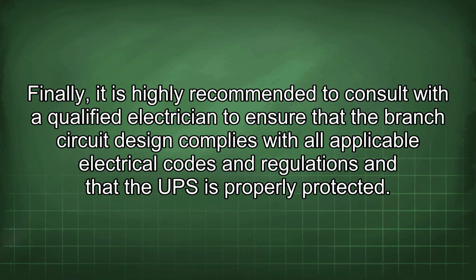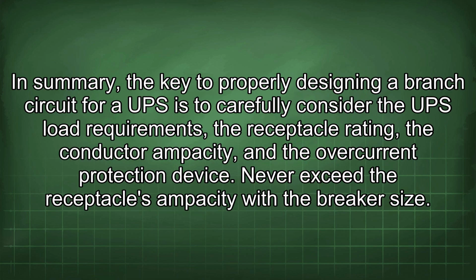Finally, it is highly recommended to consult with a qualified electrician to ensure that the branch circuit design complies with all applicable electrical codes and regulations and that the UPS is properly protected. In summary, the key to properly designing a branch circuit for UPS is to carefully consider the UPS load requirements, the receptacle rating, the conductor ampacity, and the overcurrent protection device.